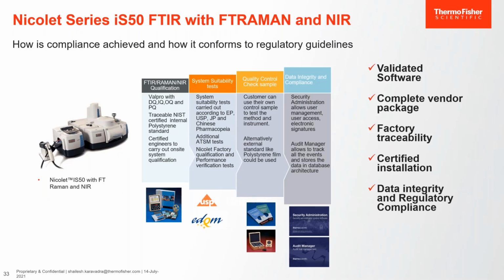We have a research grade spectrometer, the iS50R, which can be combined to do multiple tasks, whether you are doing mid-infrared monograph testing, raw material ID with Raman, or polymorph testing with Raman, and you also want to do conformity analysis with near infrared. This spectrometer can combine all three techniques into one, and therefore you need a design qualification, IQ, OQ, and PQ, which can be executed on all three techniques. And we have a validated software for this, which can do all of these tests.